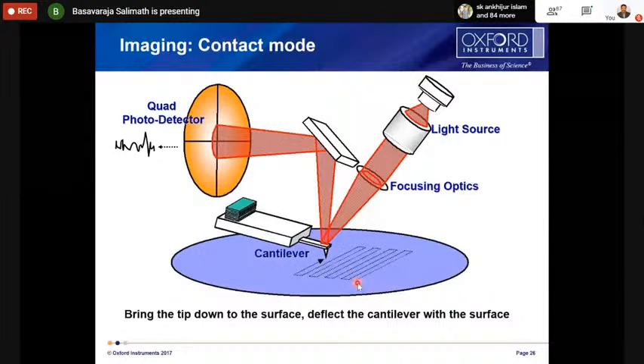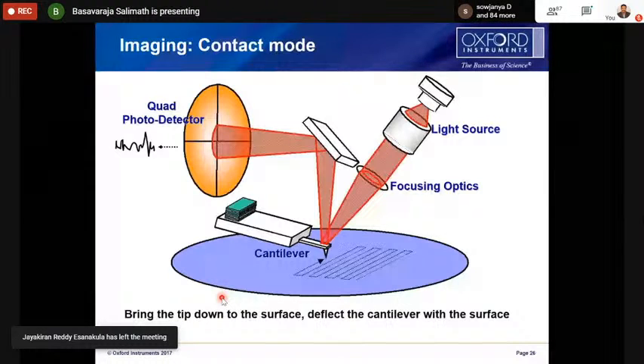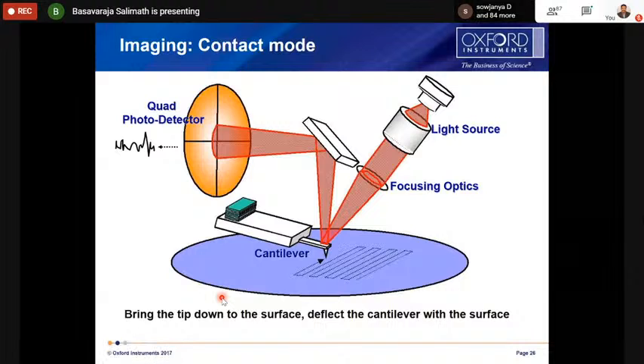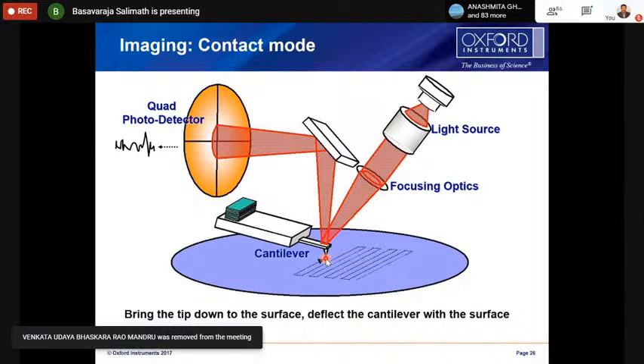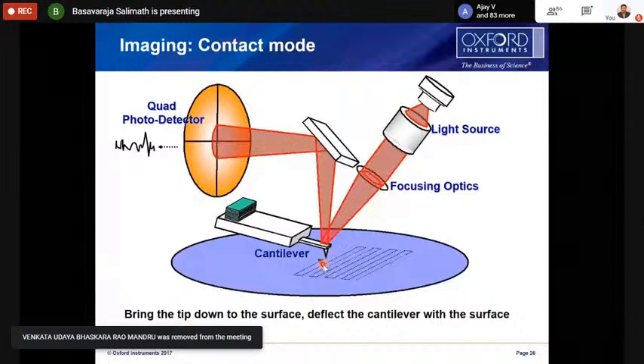Yeah. And now coming to the different types of modes available with an AFM. There are three basic modes in the AFM. One is contact mode. In contact mode, the tip is touching the sample and doing the raster scanning. So here, we are monitoring how the tip is deflecting based on the surface.